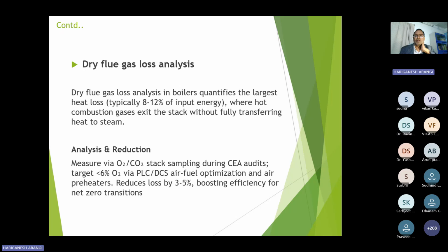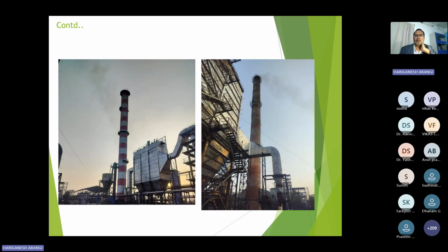And next is the dry flue gas loss analysis. Dry flue gas losses mean improper injection of air, so improper combustion will take place. The flue gases then will not exchange the proper heat when we are taking air inside, and the coal, the fuel also, we will heat it. That heat exchange will not take place properly. So you can see from the chimneys how the flue gases are coming out in color. Normally, in a well-operating power plant, you will not see any smoke. But in these pictures, I hope you can see the smoke ejecting from the chimneys.